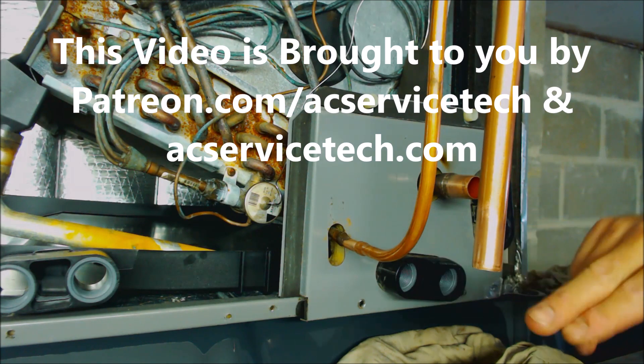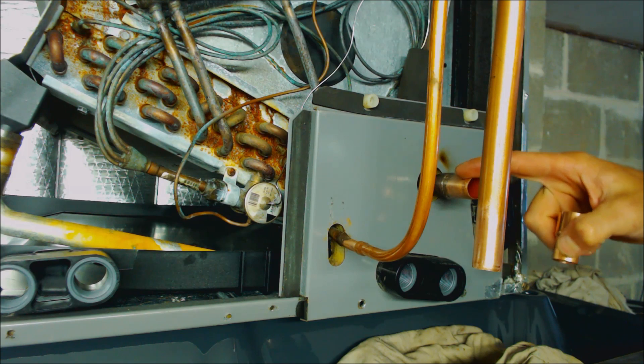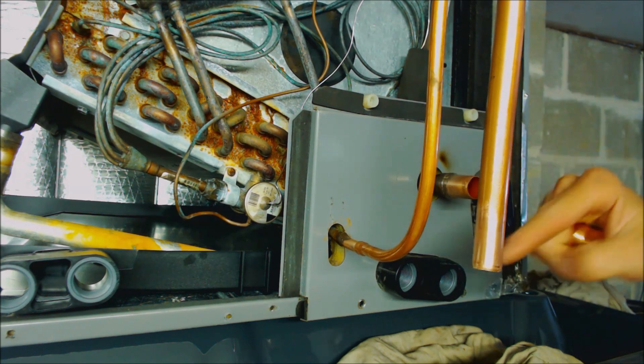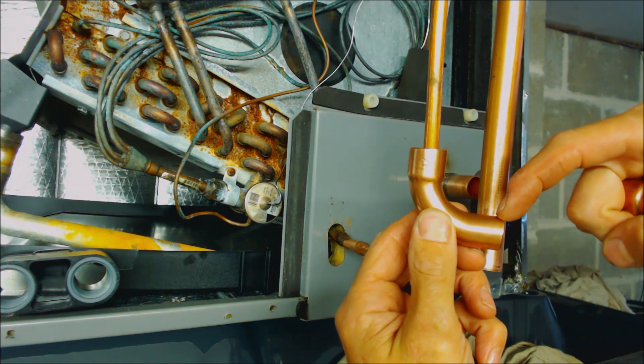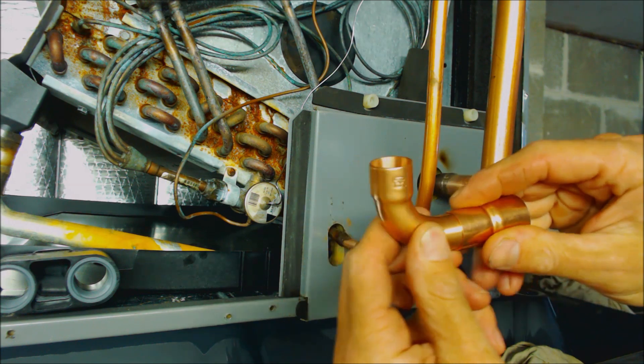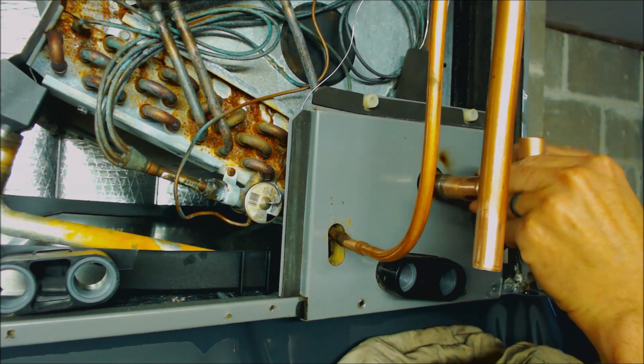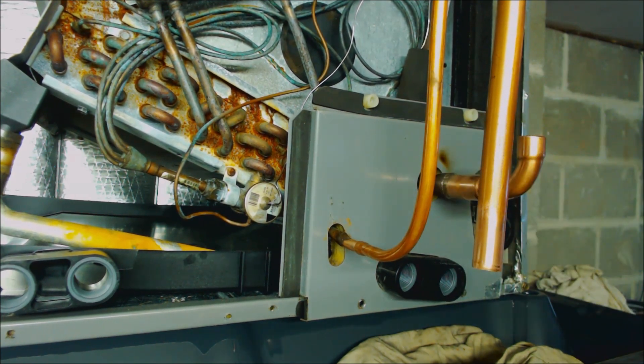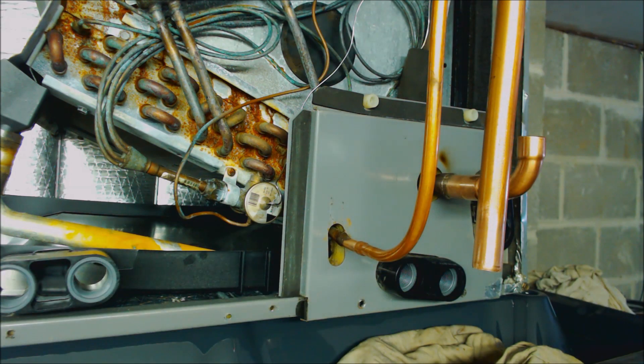We already have all of our joints cleaned. We have these as well cleaned. Basically we have seven-eighths right here and we have three-quarter here. I don't have enough three-quarter lines to do a bend, so that's why I'm using a street 90 — a long-turn street 90 — and this side is going to go into our reducing coupling right here. We're going to be using 15% silver brazing rods and we're going to be flowing nitrogen through the system while brazing.